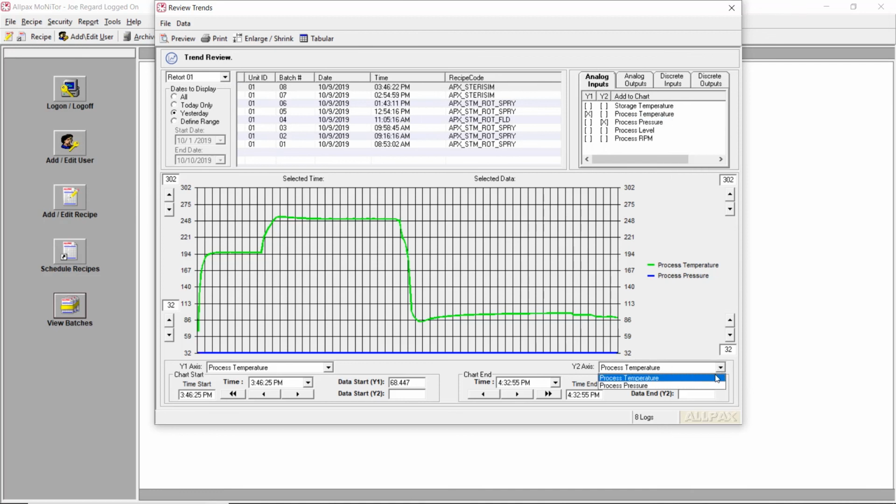Because I think your heart is skipping here too. It gets really close to 250. And then when you look at the chart, you kind of look at it and go, oh my God, I hope that didn't go over the 250 line, and it doesn't. But it'll get your attention. And I guess you could always set it to 251. You could, yeah. If you're like me and you don't like to ride that close to the edge, you probably want to go 251. If it does drop, it's still above you. Right. Yeah, if it does drop, it will deviate. It'll make a loud noise. You'll see it flashing on the screen, and it won't leave the cook step until you physically override the machine out of that step.